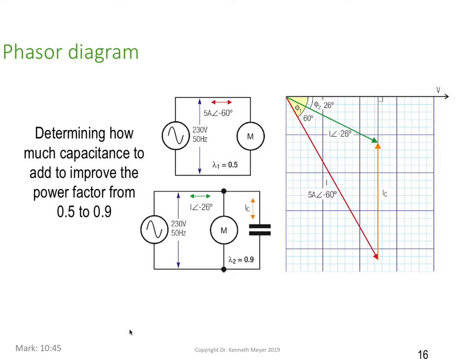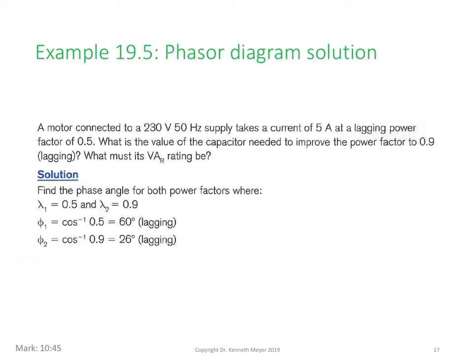So let's look at power factor correction and what we can do and how we can determine it and what we can do to correct power factor. So on this little exercise, we're determining how much capacitance to add to improve the power factor from 0.5 to 0.9. I'll just get my cursor pen up and running. So at the moment, we've got 0.5, and that's what 60 degrees gives us. You can see up here, 60 degrees. So we've got a 0.5 at 5 amps, and we want to bring it back to 0.9. So we want to add a capacitor.